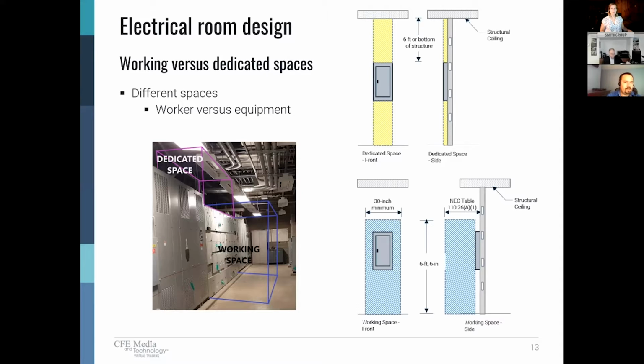So as we work within electrical rooms, our design needs to be cognizant of some spaces that we need to allocate for electrical equipment. Two that are very important to electrical switchgear, switchboards, panel boards, and the like are dedicated space and working space. Now, there's different motivations for having these two spaces reserved within the electrical room. The dedicated space is primarily to serve the equipment. It's to allow conduit, an exit and entry point from the gear. It's really to serve the equipment in that installation. The working space, as the name implies, is really for working, for inspecting, for maintenance purposes, and those type of activities that are going to occur after the installation is complete.